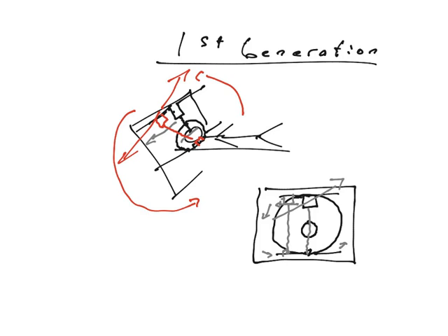Now, this was good. It was still a little slow. It still took sufficient amount of time where things like chest imaging and things like that were not feasible. Basically, this would take on the order of about 20 minutes per slice.